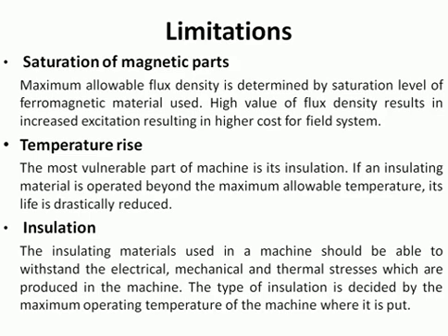Next major limitation is temperature rise. It must always be ensured that the temperature within the machine is within permissible limits. Otherwise, the various insulating materials used inside the machine, when exposed to high temperature, either get burned or gradually have their life drastically reduced. So in order to avoid such problems, you have to ensure that the machine has a proper cooling system or proper ventilation, so as to avoid the temperature rise above the limited values.